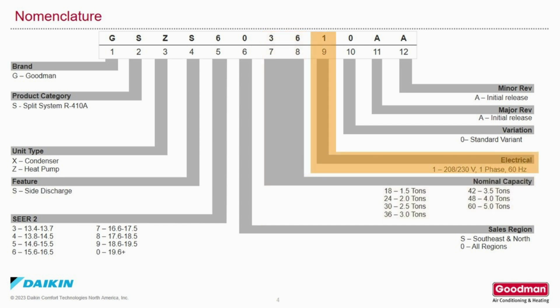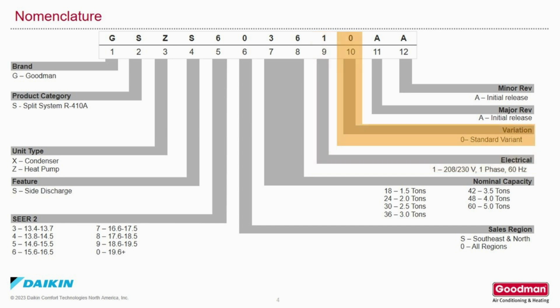The next position is for the electrical requirements. 1 is 208/230 single-phase power. The next position is a variant. 0 means it's a standard unit. The next position is a major revision. A shows it's an initial release. The last position is for a minor revision. Again, A is shown here as the initial release.